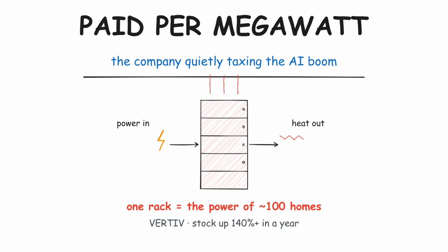Here's a number that should stop you for a second. A single top-end AI chip draws around 1,000 watts, running flat out around the clock every day of the year. Now put 72 of them into one cabinet, and that single rack pulls roughly 130 kilowatts. That's the electricity demand of about 100 homes, standing in a slot not much bigger than a wardrobe.